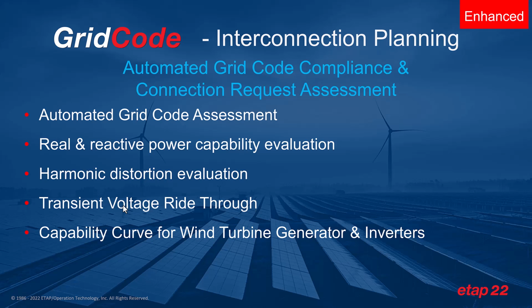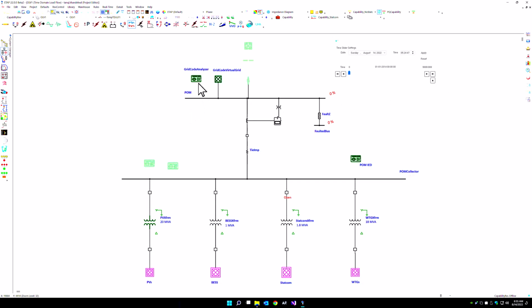So let's see our automated grid code compliance in action. We can use our grid code analyzer within this particular electrical system that has PVs, energy storage, STATCOM, and wind turbines to essentially determine which devices are being monitored and controlled. And of course, based on our grid code analyzer, we can also define specifics of the capability curve in this PQ and VQ capability in terms of the minimum sweep and the maximum sweep of voltage as well as power within the particular simulation.